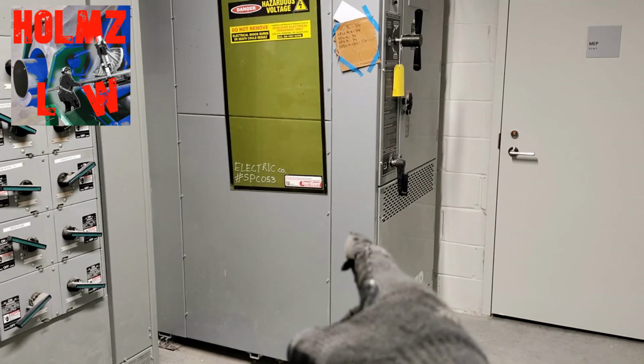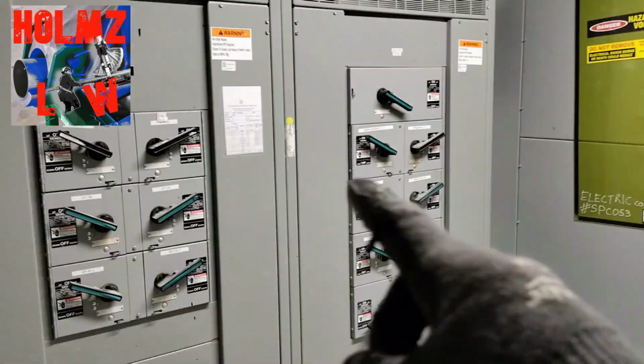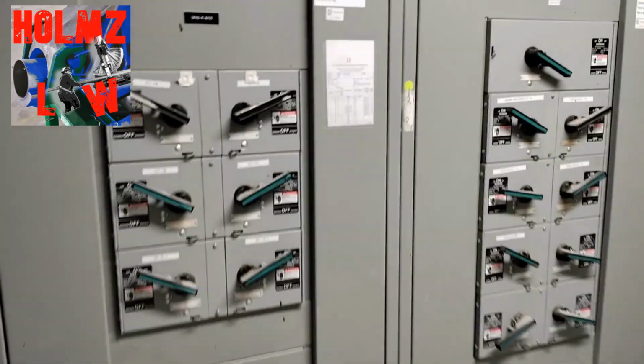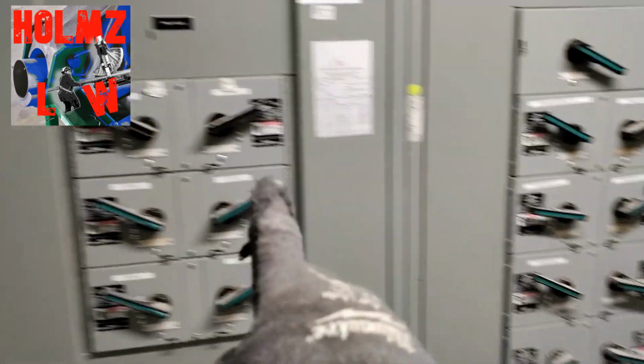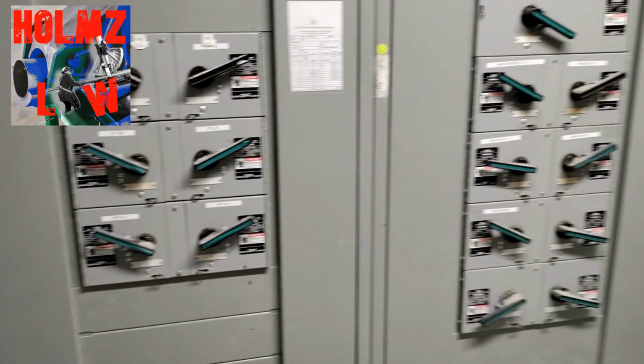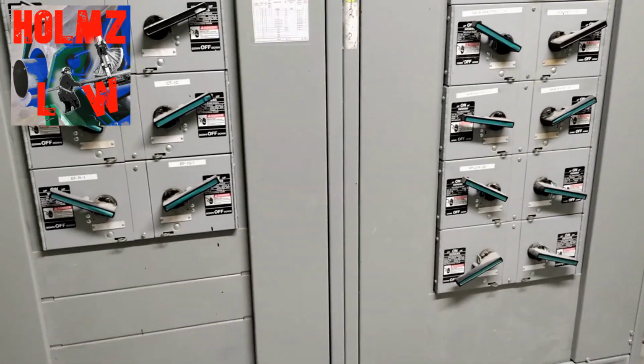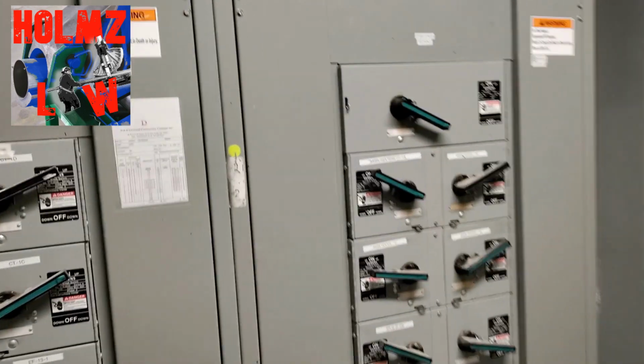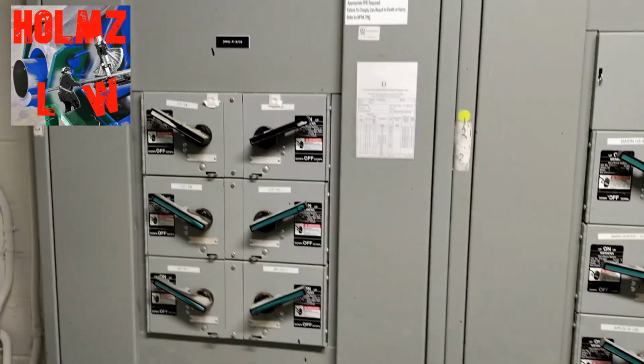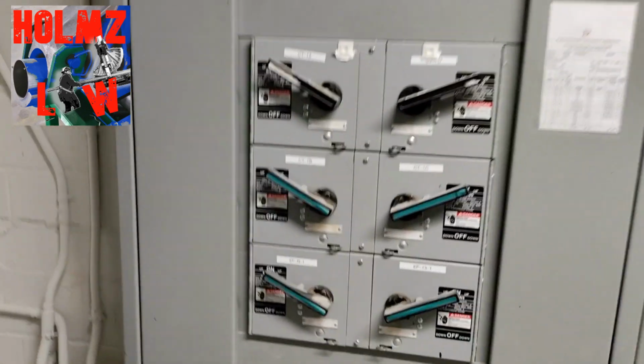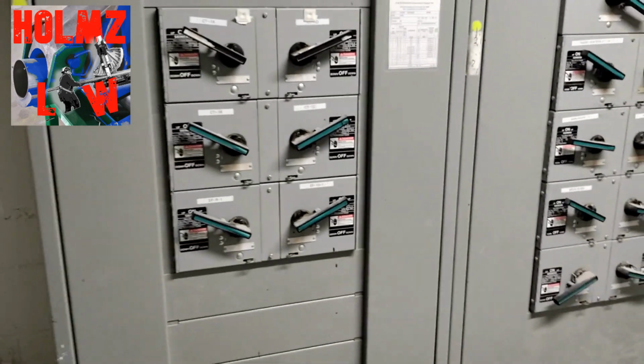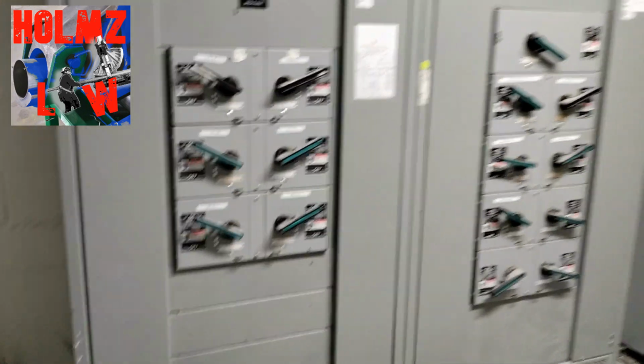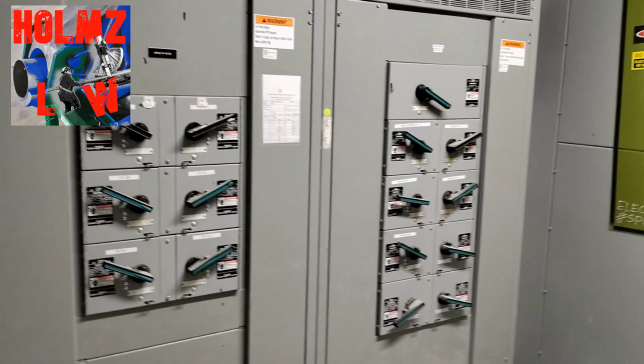So this ATS here is controlling the optional standby distribution panels. This panel is backed up by the generator. If the generator ever kicks on, it's going to feed this whole panel, which is feeding the basin heaters, the cooling towers, a couple of panels, and some exhaust fans. So they're backed up by this distribution panel.